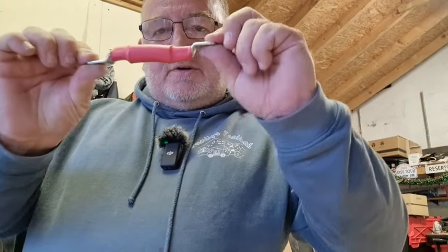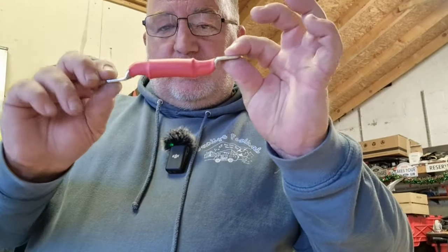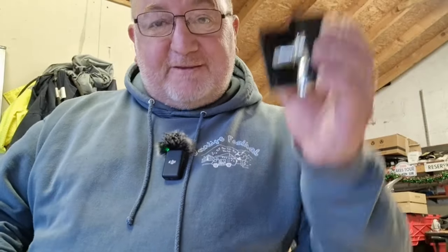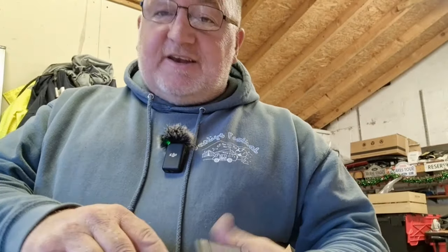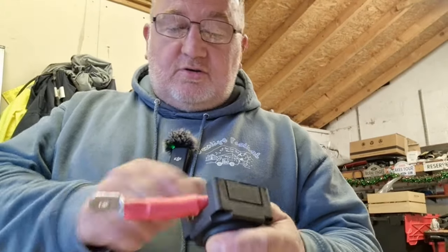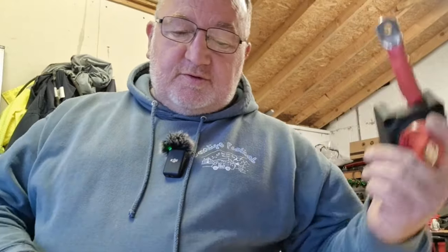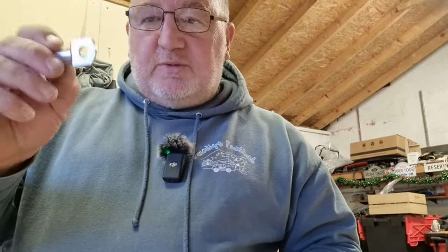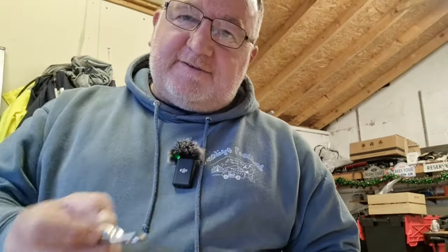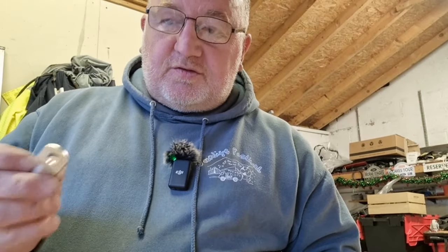So I've got a 10mm hole this end, 8mm hole that end, because there's an 8mm there and a 10mm on that one. It is all right to mix and match your lugs, as long as you're putting the right ones on the right end. Don't have too big a gap — I wouldn't put a 10 on an 8, because it's the contact area you're after.